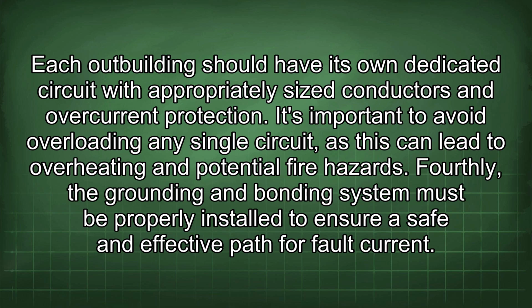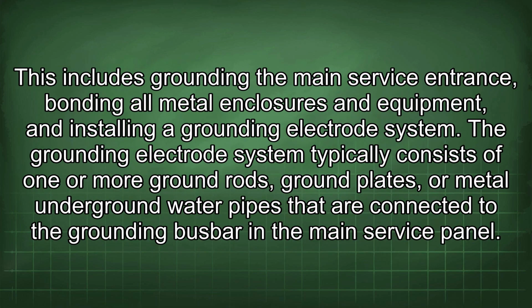Fourthly, the grounding and bonding system must be properly installed to ensure a safe and effective path for fault current. This includes grounding the main service entrance, bonding all metal enclosures and equipment, and installing a grounding electrode system. The grounding electrode system typically consists of one or more ground rods, ground plates, or metal underground water pipes that are connected to the grounding busbar in the main service panel.